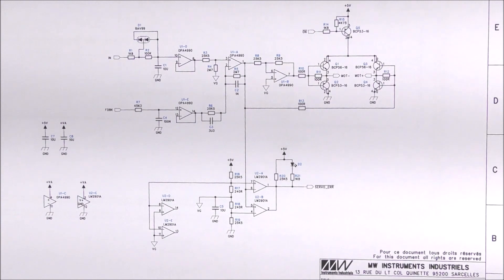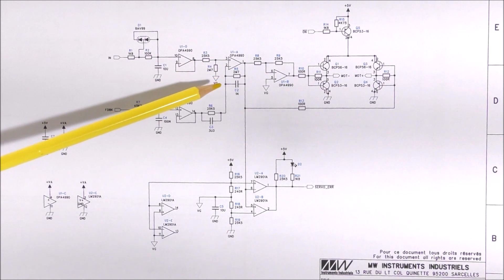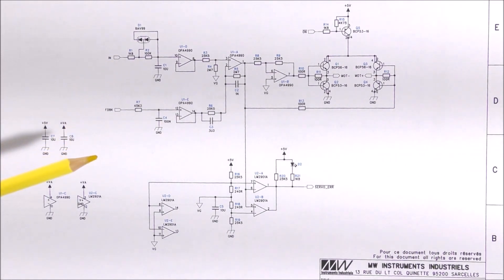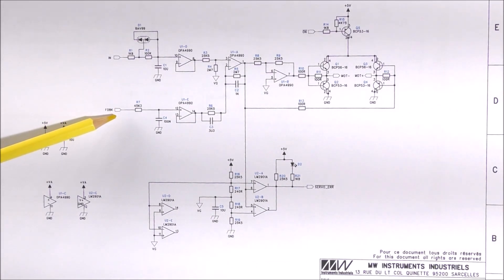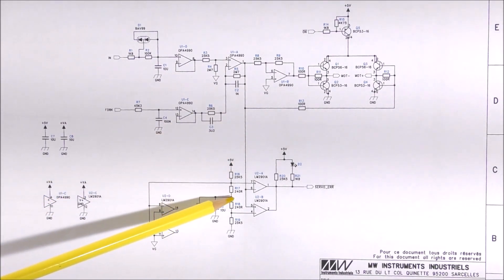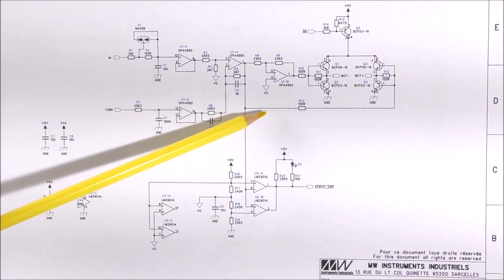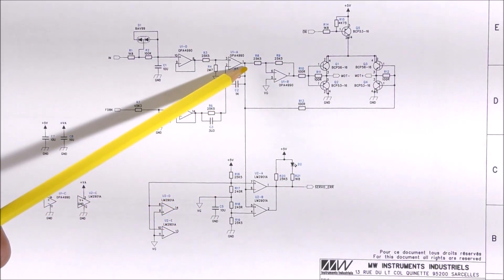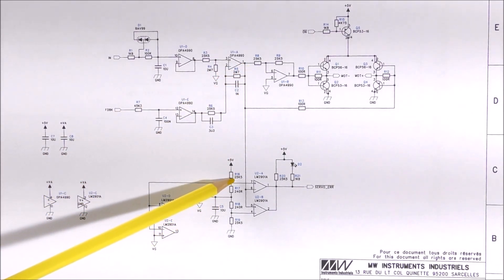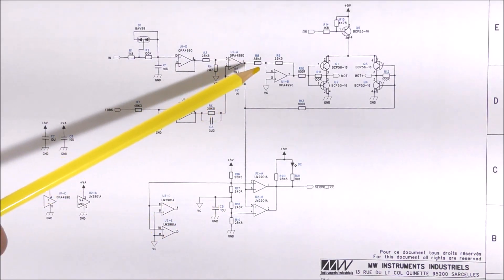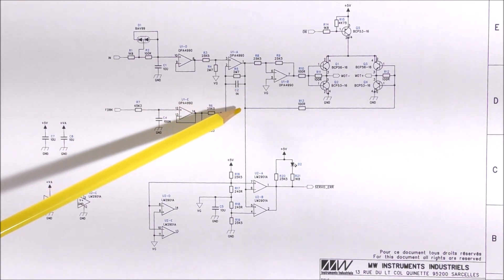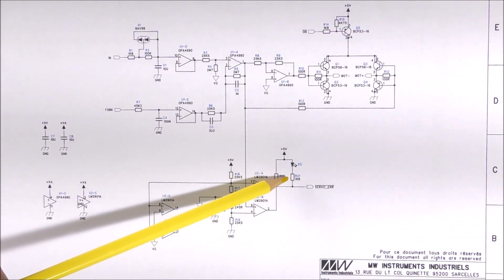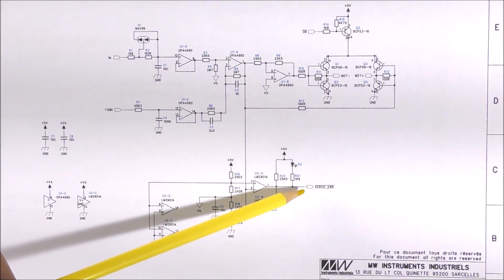The schematics of the servo control is here. There is a differential amplifier with high gain. One input will be connected to the output of the DAC — this voltage sets the position of the shaft of the potentiometer — and the second input is connected to the wiper of the feedback potentiometer. There is a virtual ground at mid power supply, approximately 2.5 volts, and a power stage which permits to drive the motor. There is also detection of failure of the servo control: the output voltage of the servo amplifier is compared with two thresholds close to the virtual ground. When the servo control works normally, this voltage should be close to the virtual ground; otherwise a low level will be indicated using a small LED on the PCB, and the signal will also be fed to the microcontroller of the main board.